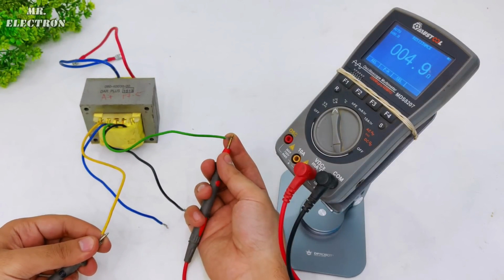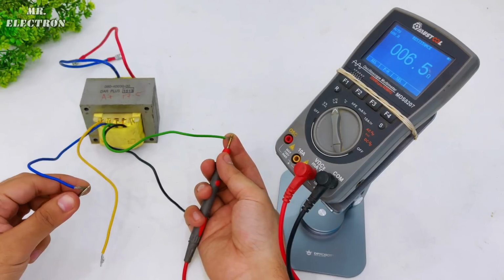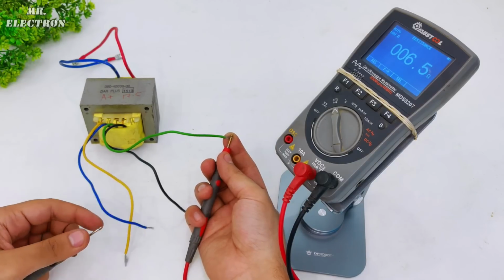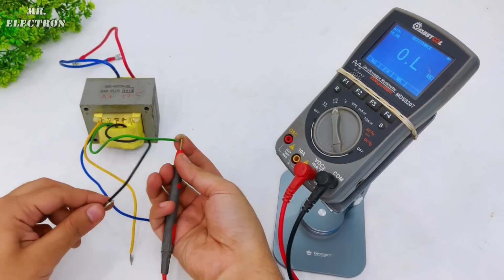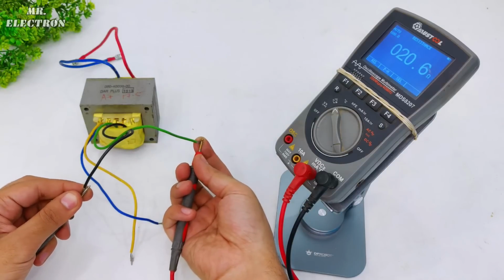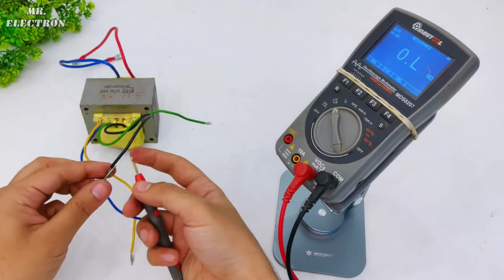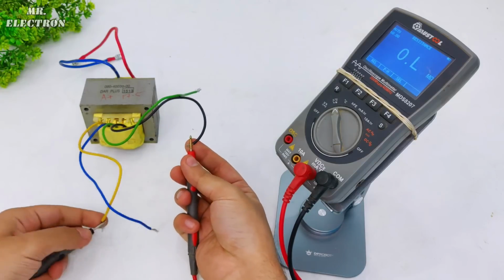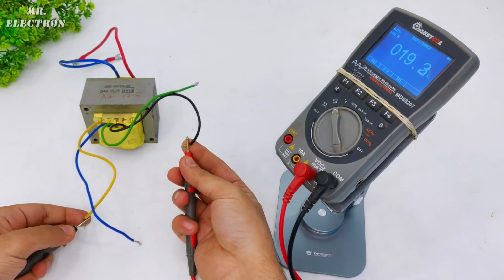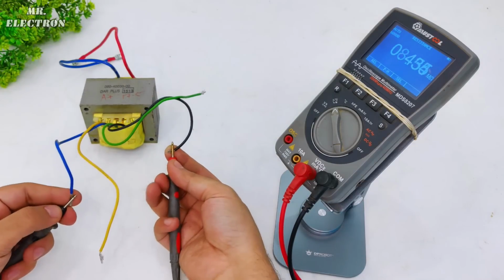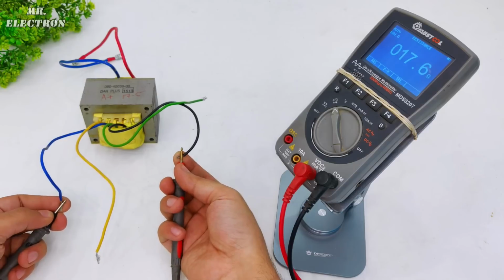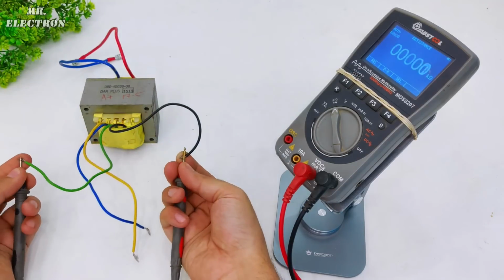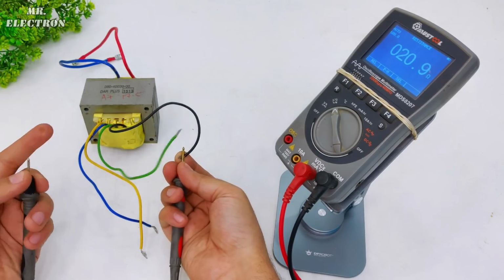First, take green as common and keep changing the other wires. Here we have 4.9 ohms. 6.5 ohms, way too less. Green and black, 20.5 ohms, that's very high. So none of these. Now taking black as common, then yellow, 19.3 ohms, very high. Blue, 17.6, and green around 21 ohms. So blue is, I think, what we need here.